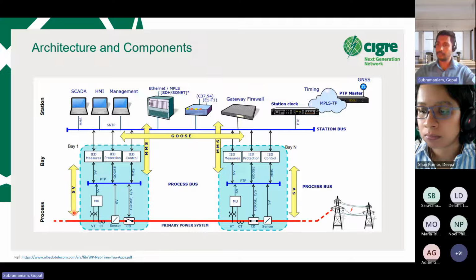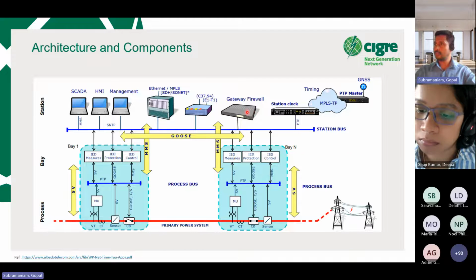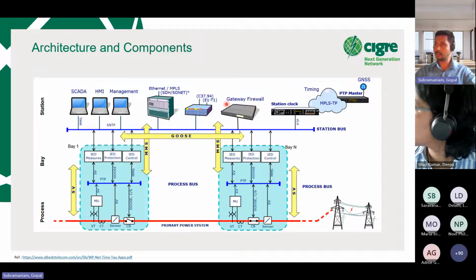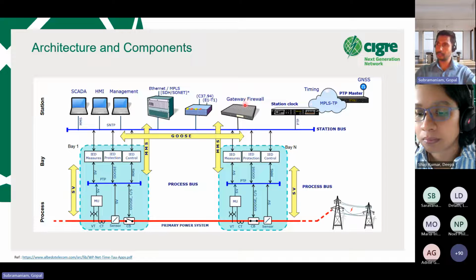And as you see, like sample value, which we generally see in a fully digital substation, where the analog quantities from voltage transformers and current transformers will be converted into a digital value, and then fed into a process bus. And then other components, as you might see, like a gateway and firewall, which can also be used to monitor and protect the system when it is interfaced with the network control center, and which also acts as a protocol converter. And then we have clocks.